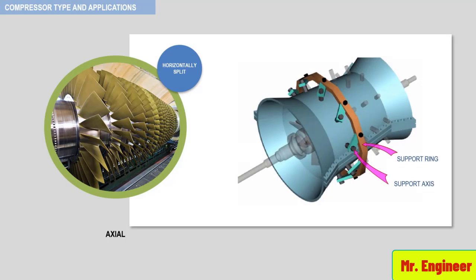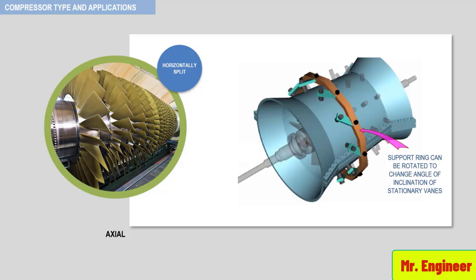In general, the stationary vane arrangements are guided by supporting rings for variable flow requirements. On rotating the supporting rings, the angle of inclination of the stationary vanes can be changed. This is used to change the performance parameters when required. The following illustration gives a clearer view of the stationary vanes changing the angle of inclination simply by rotating the supporting rings.